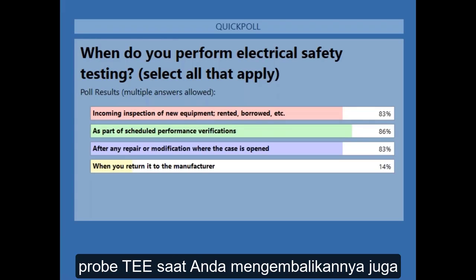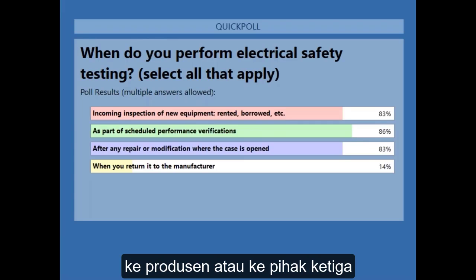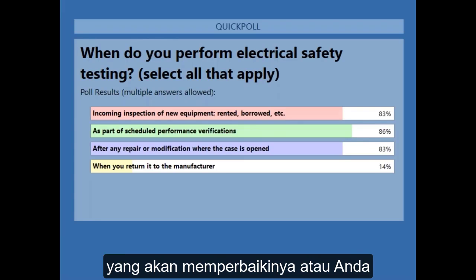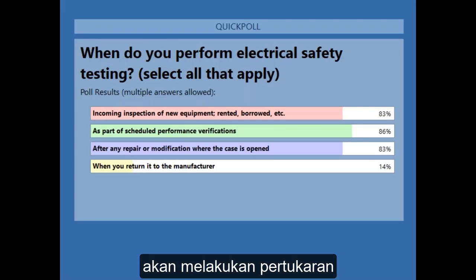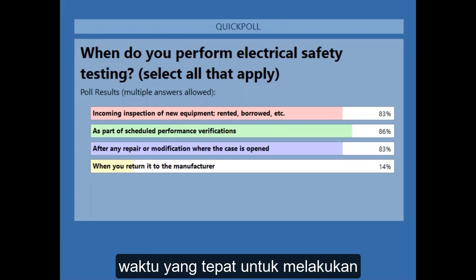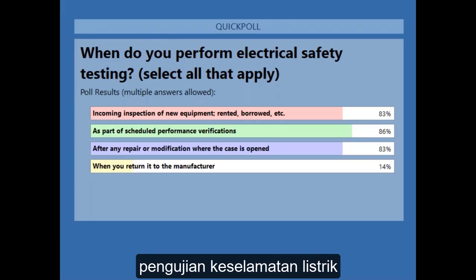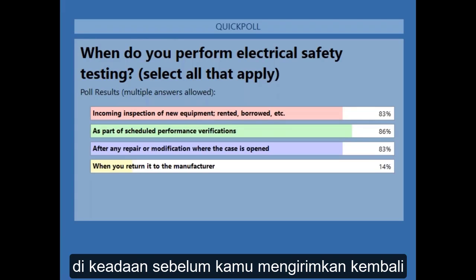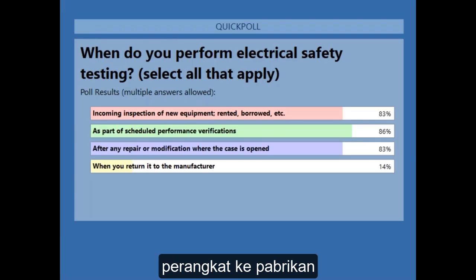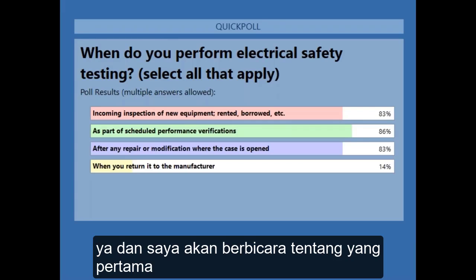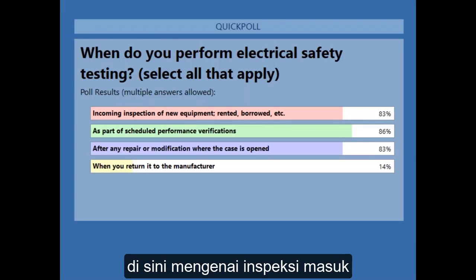when you return it either to the manufacturer or to a third party that's going to refurbish it, or you're going to do an exchange. That's a key bit of information that's important to them. So that would be a good time to do electrical safety testing, as you or before you return the device to the manufacturer. Yeah, and I'll speak to the first one here with incoming inspection.